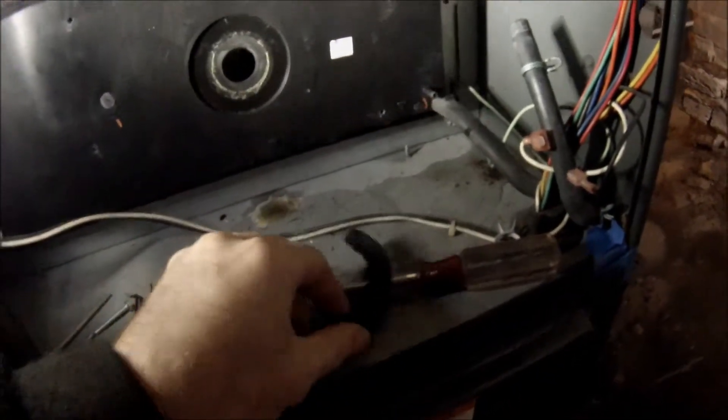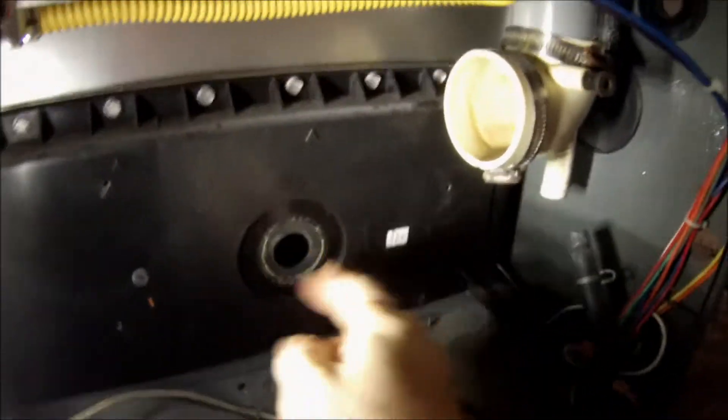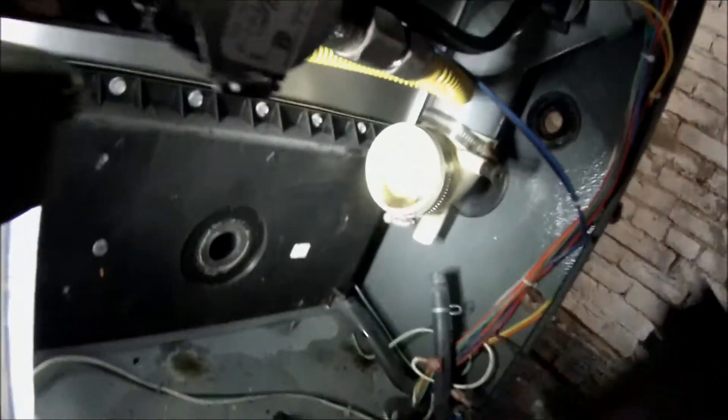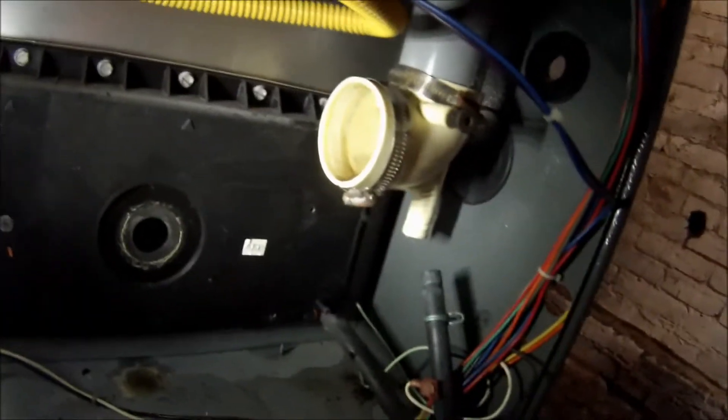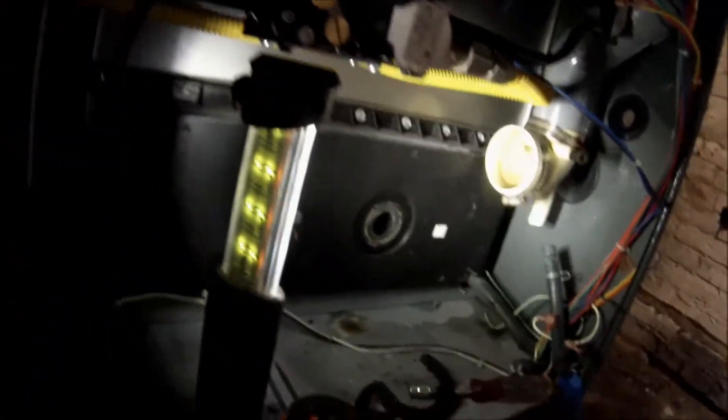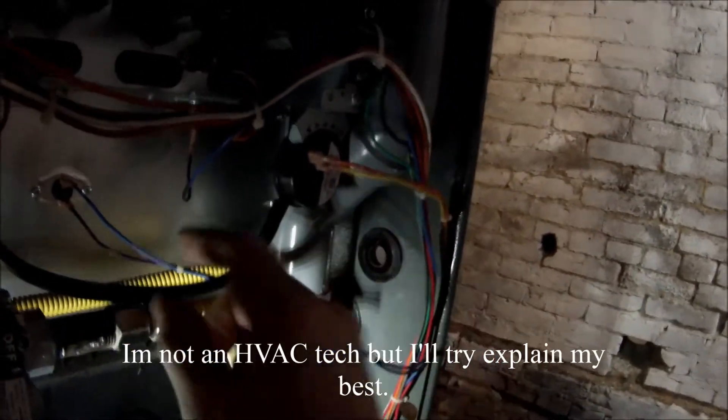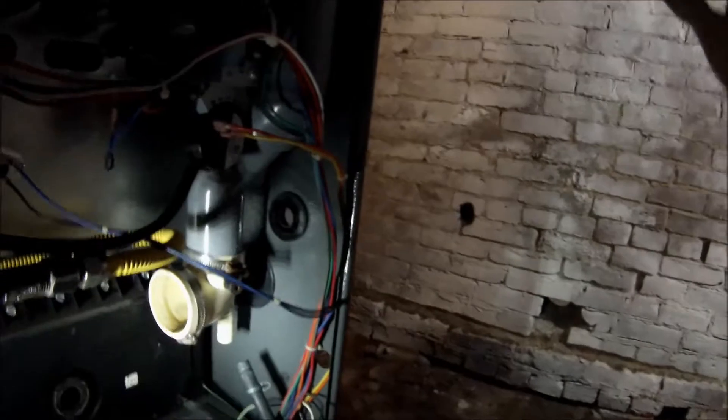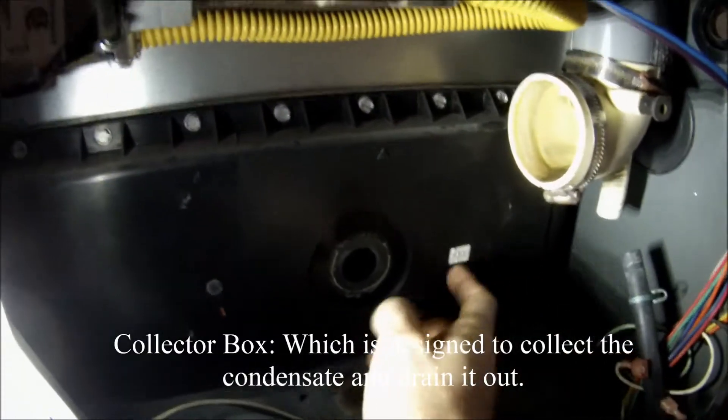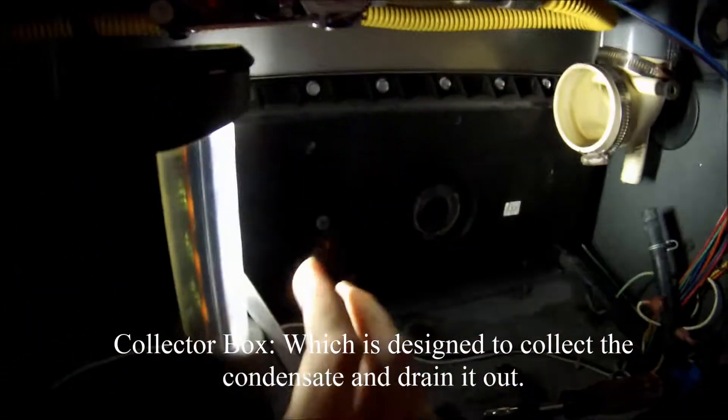How thick that is and how bad this one is. So what's happening is this inducer motor, it sucks the air in through the back right up on there. It sucks the air out of this hole right here. So it sucks the air out. And what that does is there's a pressure switch. And here's the pressure switch right here. Let me show you. There's two of them on this one. It's a two stage furnace. So there's one pressure switch here and there's one there. This one detects if there's getting air out of the inducer out, you know, out to your street or wherever it's going, your exhaust. And the other one, this one here is getting it from this, this right here, this little container, this little plastic piece.